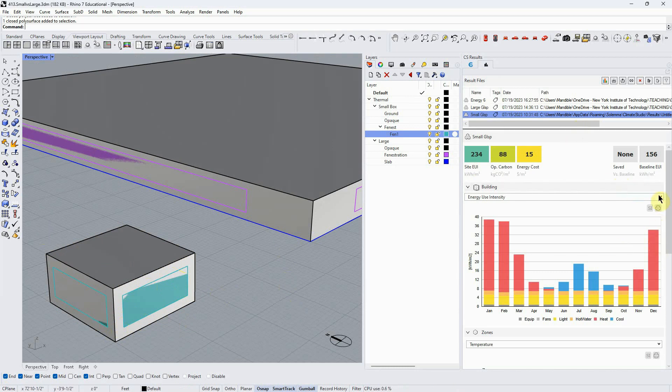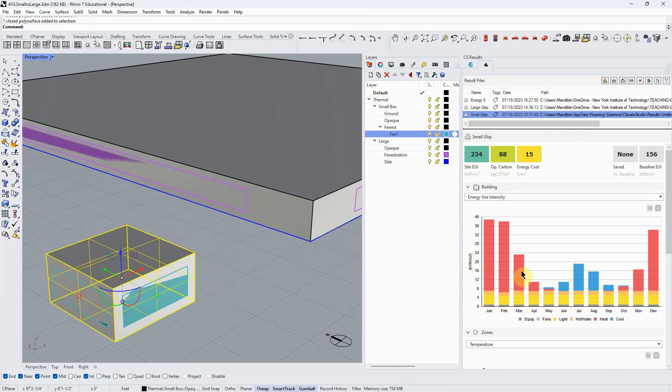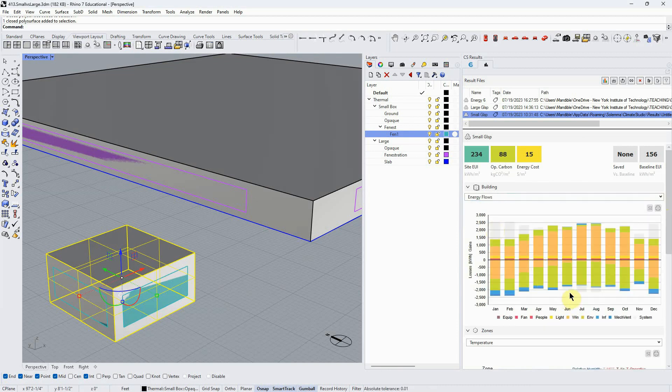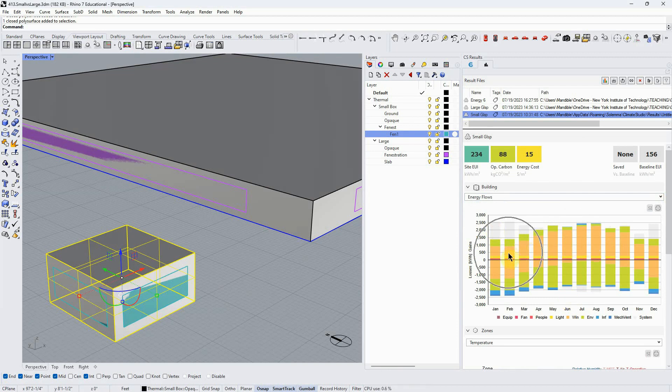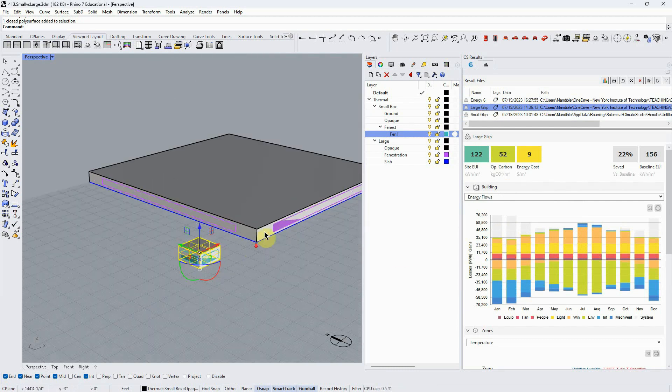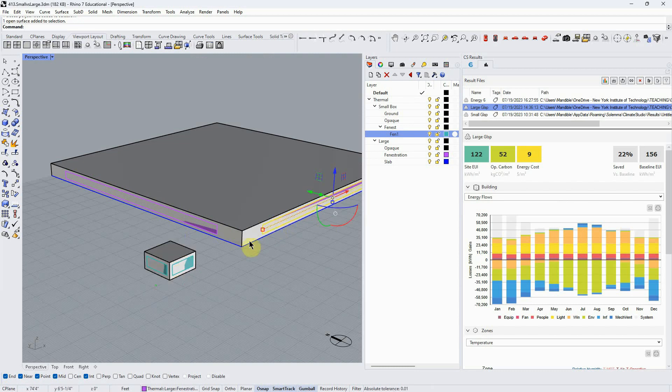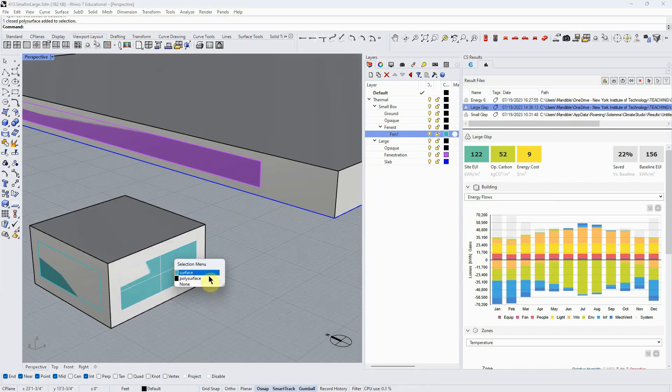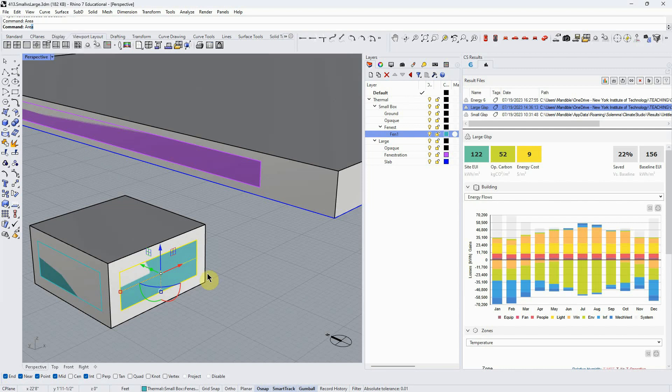Let's take it a step further and see if we can analyze why that's true. In our small building, this is our energy use intensity graph. We've got a lot of heat load, less cooling load but still plenty of cooling load. Let's look at our energy flows. We obviously remember that the orange is the windows. We have a lot of heat gains in the summer and not as much in the winter, so that's pretty bad—that's exactly the opposite of what we'd like to see. If I switch to my larger building, you see that the effect of the windows has been reduced drastically because the percentage of window to wall—that's another thing, window to wall ratio—is something you're going to hear.